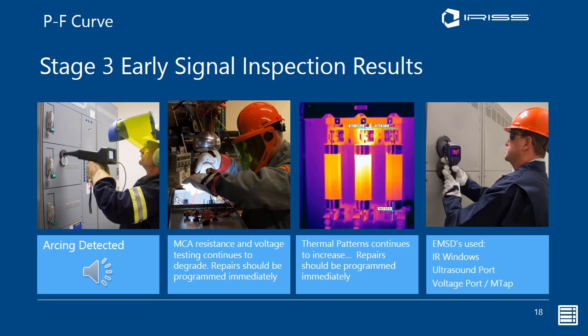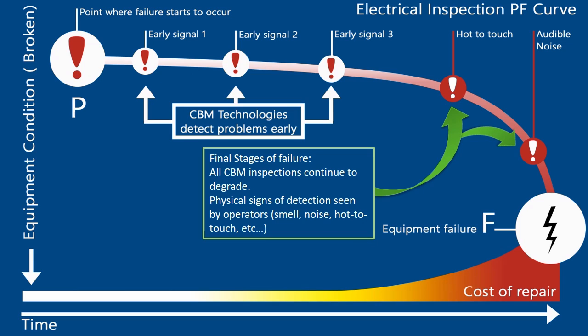When we get to the final stages of failure, this is when we start to see the physical signs of detection for the operators, who may hear noises, smell burning. Equipment might be hot to touch. The way the equipment's running is not its normal operating mode, and operators become very, very astute when it comes to their equipment. They're used to how it should run. The likelihood at this stage of being able to repair the components within the equipment becomes less viable because it's been left too long. So the repairs start to become much more expensive if we allow the faults to get to this stage.